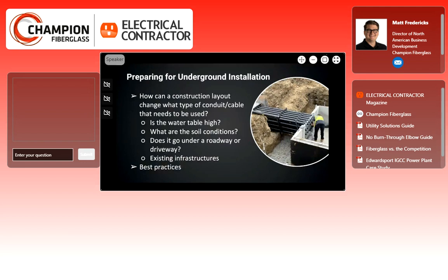You also want to pay attention to the soil conditions, caustic or corrosive or not. Is the water table high? Does it go under a roadway, driveway, or parking lot? Those are all things to consider when thinking about what type of conduit and cable you need, and how you're going to construct your underground install.